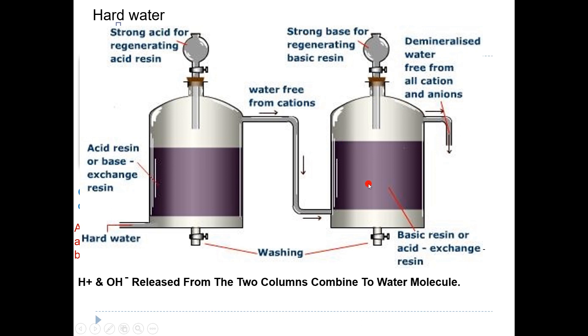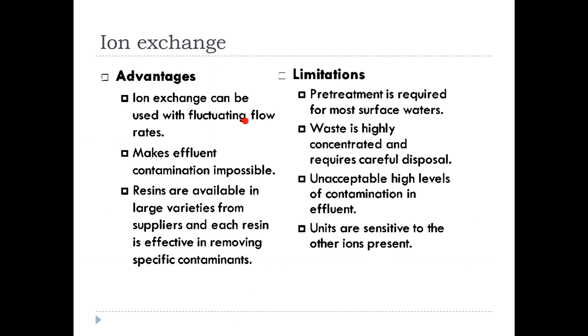After passing the basic solution, the anions on the anion exchange resin are replaced by OH– again. So in this process there are two steps: the softening step and the regeneration step. The advantages of ion exchange are: it gives only H+ and OH– ions in solution, can be used with fluctuating flow rates, and makes effluent contamination unlikely since only H+ and OH– are produced.